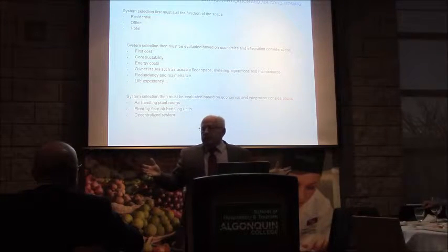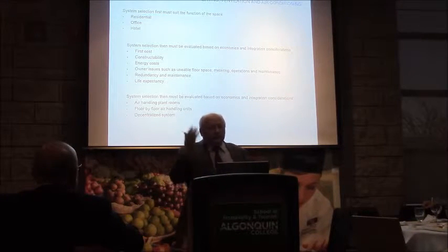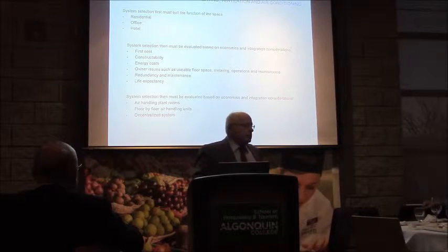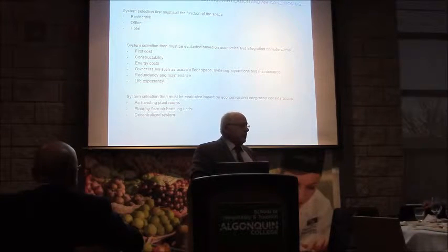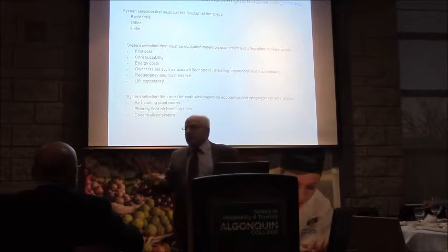If you have a 20,000 square foot floor plate, after you've done 5 floors, you're at 100,000 CFM moving around. That's not a small shaft at that point.